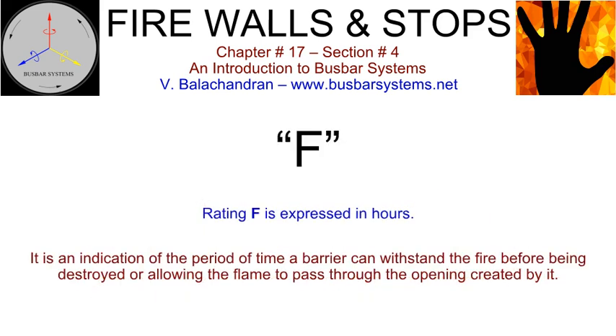Rating F is expressed in hours. It is an indication of the period of time a barrier can withstand the fire before being destroyed or allowing the flame to pass through the opening created by it.